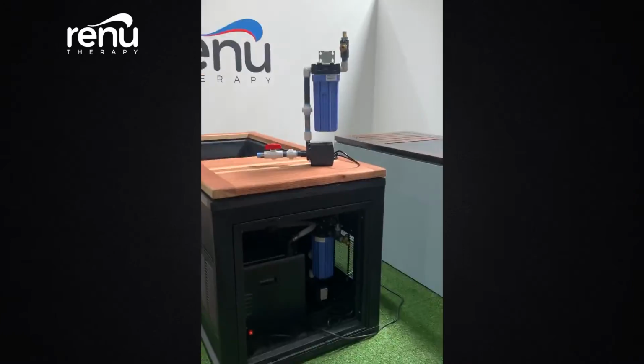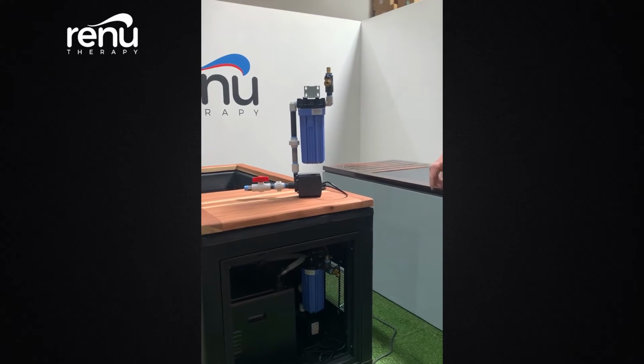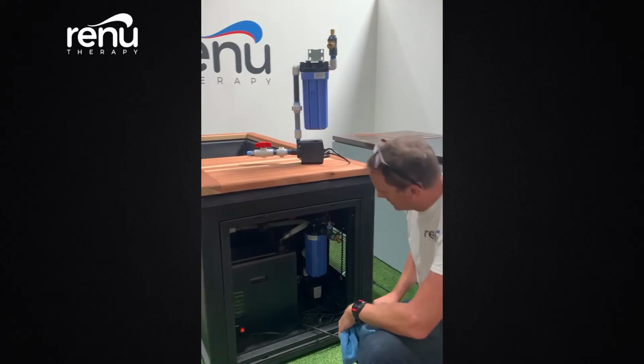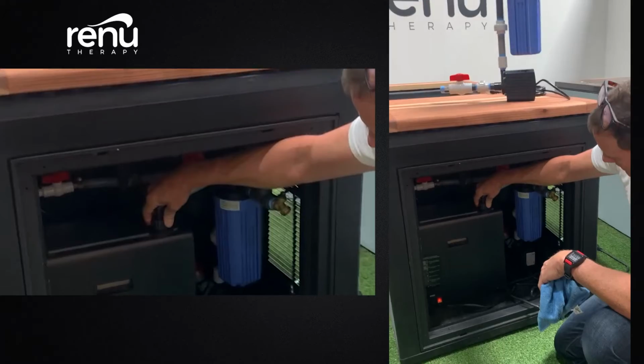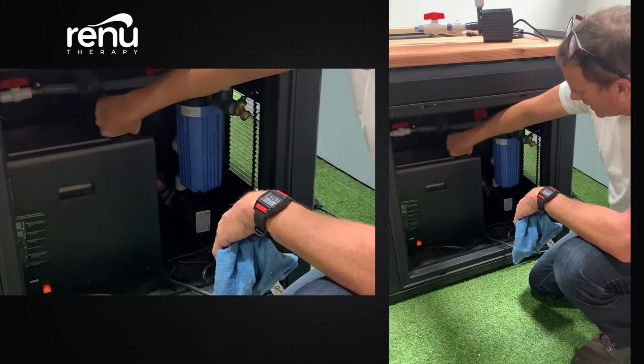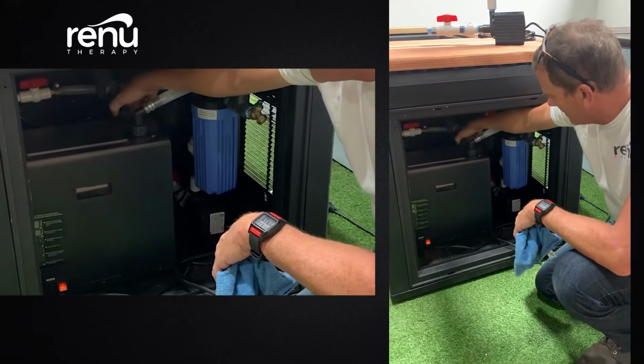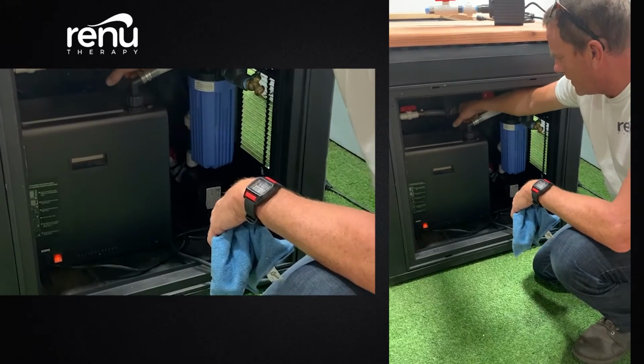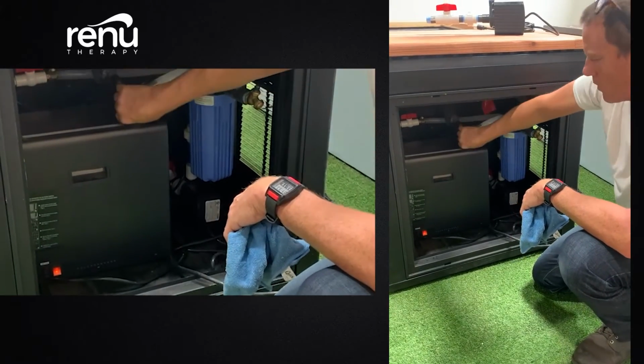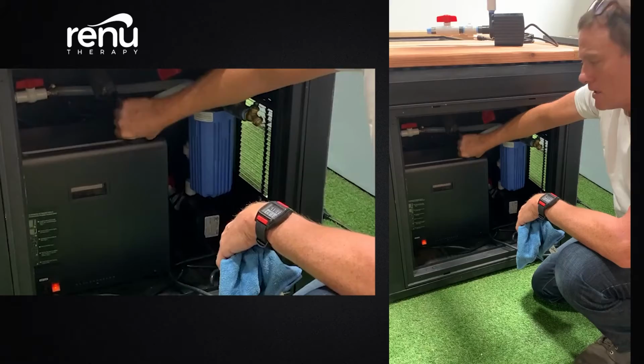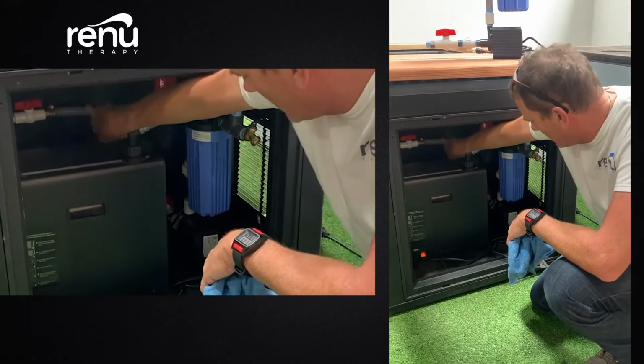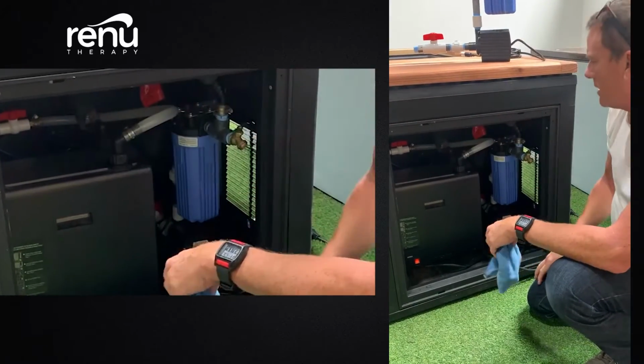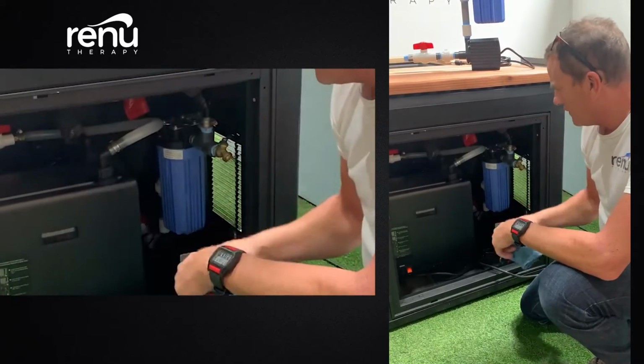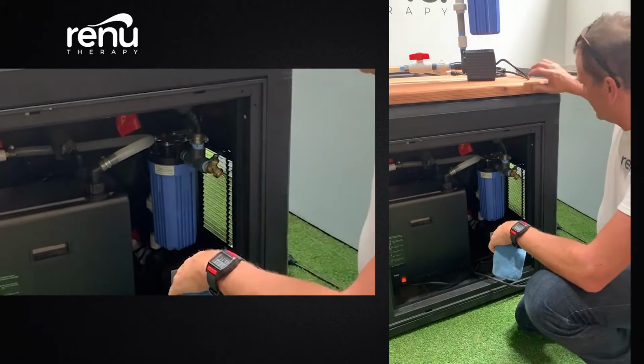Another thing that could happen is where the chiller connects. There's these chiller nozzles, and these are hand tightened, and a lot of times people won't tighten them down very tight. There's a rubber cork in there that has to be compressed. So you just want to make sure that those are nice and tight, dry it off, see if that stopped any kind of leaking. Another thing that could be a problem is low water flow.